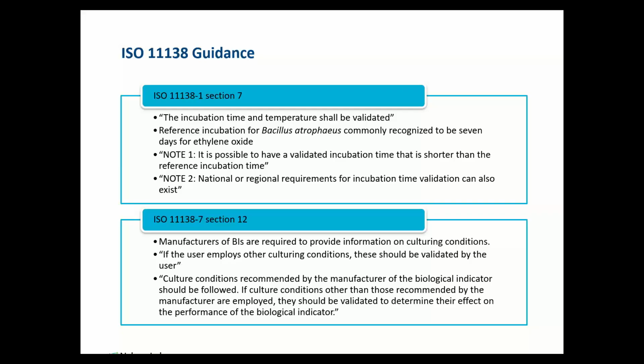The second section of ISO 11138, so this is actually section 7, -7, section 12, states that manufacturers of BIs are required to provide information on culturing conditions. So this is so that we can follow what's already been established by the manufacturer as an acceptable culture condition approach. So that would be temperature, incubation, media type, and potentially volume. This section also states if the user employs other culturing conditions, these should be validated by the user. So again, it's important to pay attention to the language here. This is where the word should is used, so that means it is a recommendation, and this is what Nelson Labs has already completed for the RapidCert BI test.